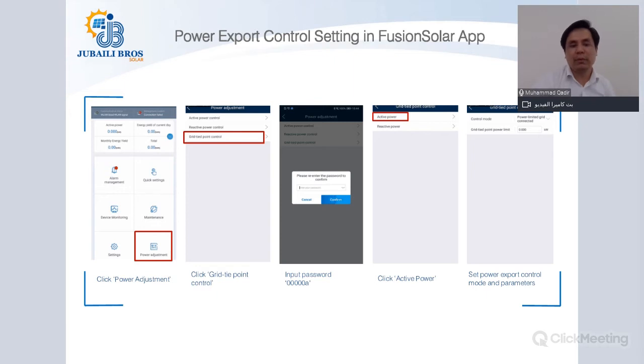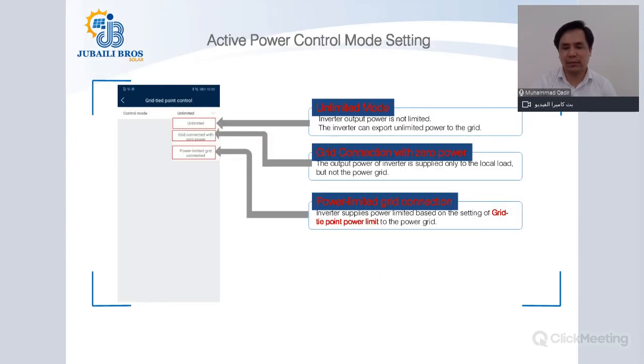So the password by default from the Huawei side is 5 times 0A. After putting that password, it will lead you to the option of either active power control or reactive power control. Since our purpose is usually active power control, you will click that, and that will prompt you to the next window. So now you have the option of set the power export control mode and parameters. You will click that, and then the next slide will tell you what next options you will have.